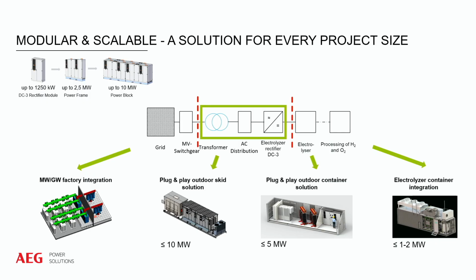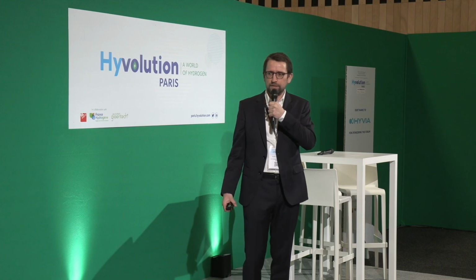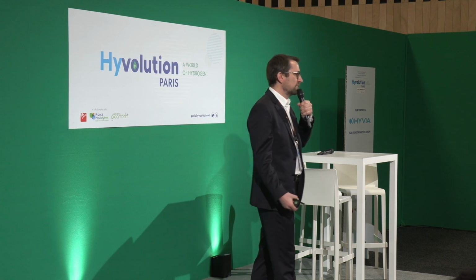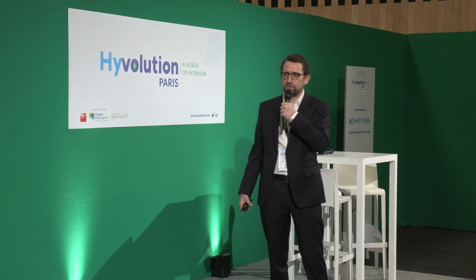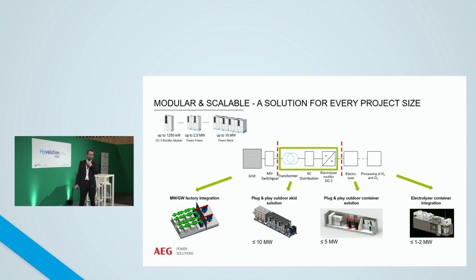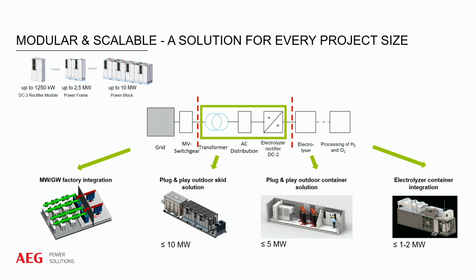We provide these in different packages according to customer power requirements. For smaller projects of 1 to 2 megawatts, we normally fit the equipment directly into the electrolyser OEM's container. For higher powers, we provide a plug-and-play outdoor container solution. For even higher powers, where transformers get too large for a standard container, we provide a plug-and-play skid solution. We can also integrate our equipment into any other kind of building or plant, including future megawatt and gigawatt factories.